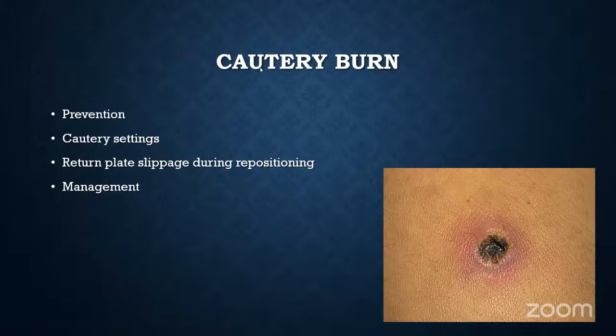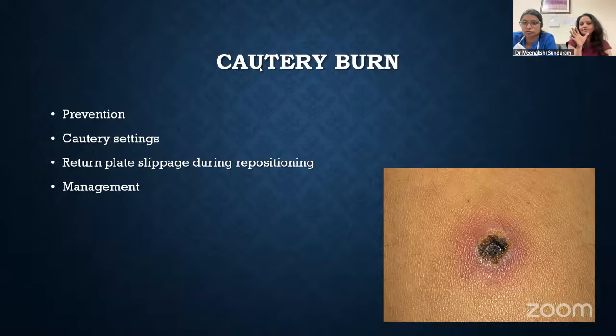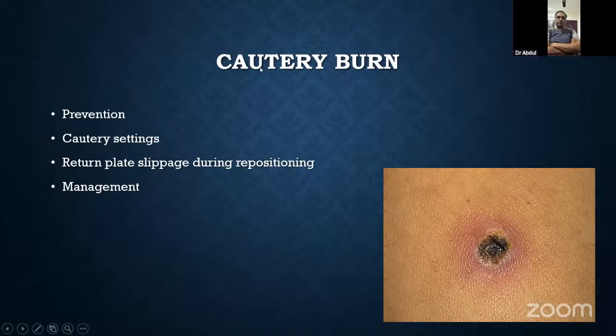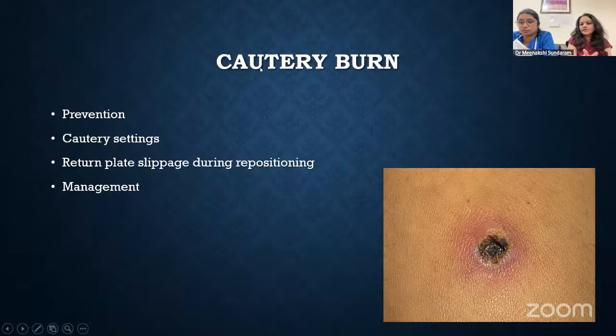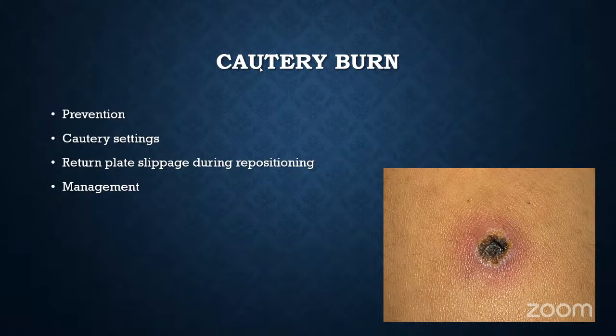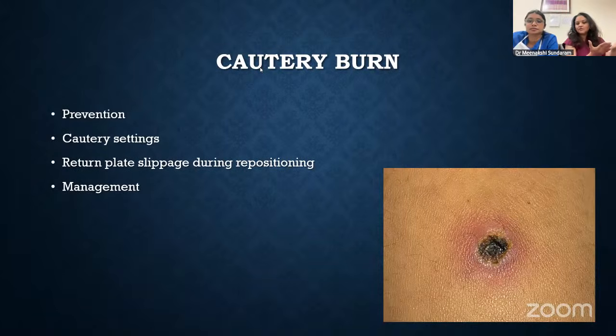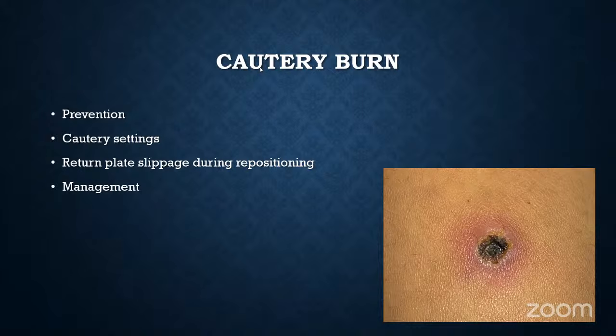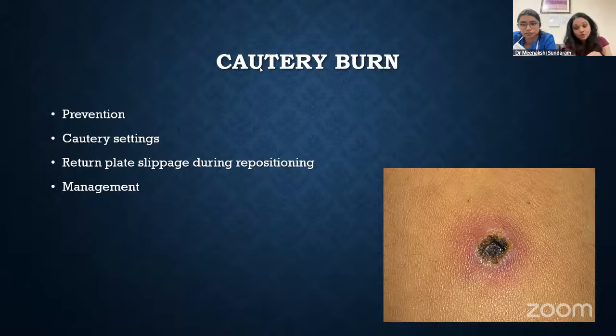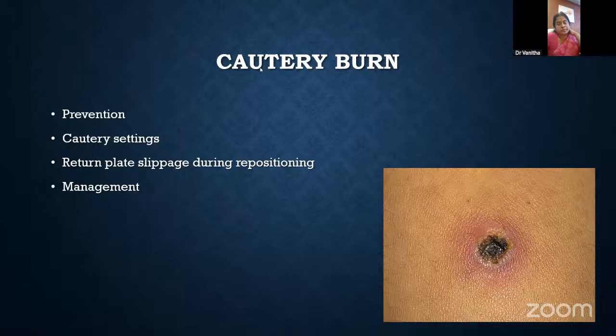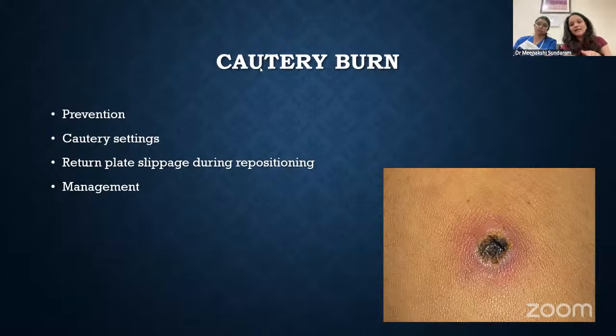So what we normally use is the disposable adhesive plates which we put on the thighs. So we generally don't have this issue during repositioning. Only when you have those black plates which you have kept under the patient's bottom, and then you are changing the position, it's a problem. When you use these adhesive return electrodes, you don't generally have that problem. So like you said, when you are repositioning with the black plates, you definitely have to ensure that it is fully in contact with the body when you are changing positions.